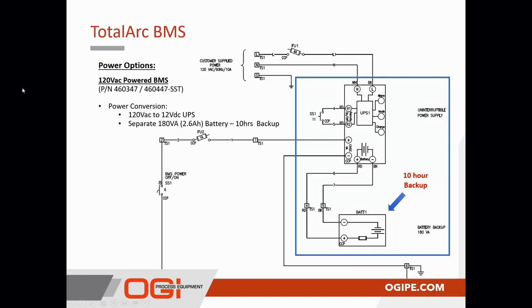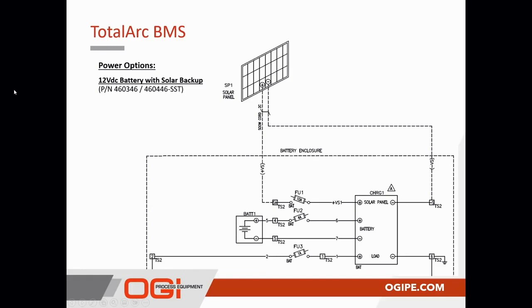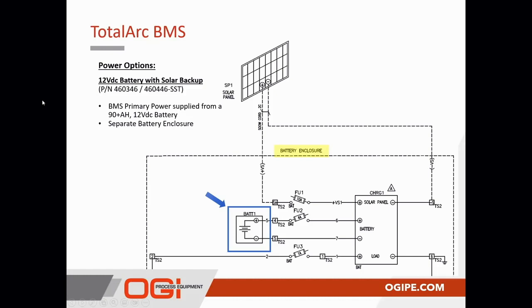For the 12 volt battery with solar package, this is the only option that's fully autonomous. In other words, essentially, no external power is required to support this control system, the BMS. Its primary power source is a 90 plus amp hour, 12 volt DC battery that is charged. It's housed in its own separate battery enclosure that is separate from the main BMS system. With that battery available to the BMS, once we lose any kind of solar backup at all, we would be able to support full BMS operation for 7 to 10 days.